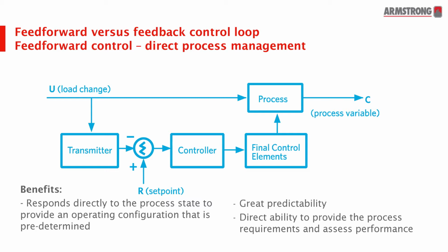So what's the best way for us to do that? And there's a map, a predetermined map of how fast the fan should be spinning. There's a map that says what the control valve setting should be, and there's a map that tells us what the chilled water supply temperature setting should be. And the feed-forward control will say, okay, for the load of 200 kilowatts of cooling, there are my set points, I just go there. So there's no hunting, it's a direct control, feed-forward method, a predictable outcome.